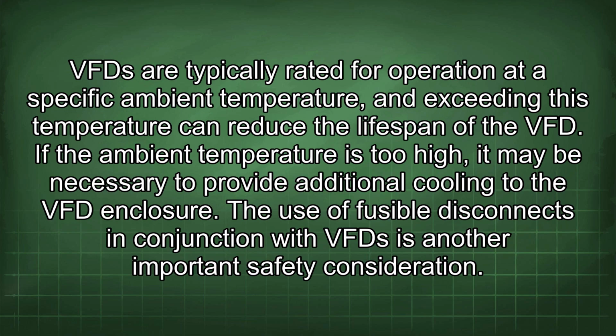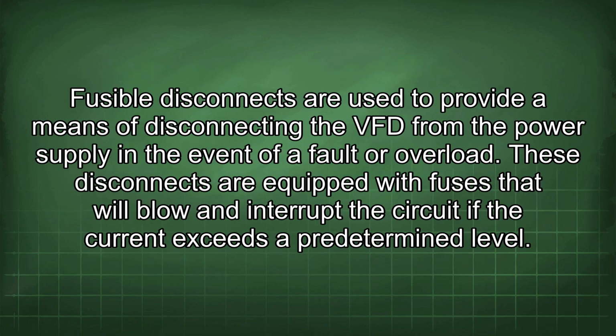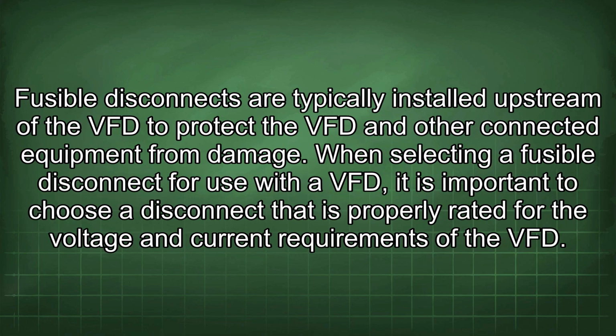The use of fusible disconnects in conjunction with VFDs is another important safety consideration. Fusible disconnects are used to provide a means of disconnecting the VFD from the power supply in the event of a fault or overload. These disconnects are equipped with fuses that will blow and interrupt the circuit if the current exceeds a predetermined level. Fusible disconnects are typically installed upstream of the VFD to protect the VFD and other connected equipment from damage. When selecting a fusible disconnect for use with the VFD, it is important to choose a disconnect that is properly rated for the voltage and current requirements of the VFD.